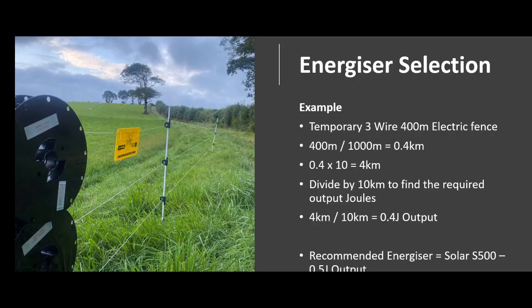Let's start with this example: we're going to erect a single 3-wire electric fence that's 400 meters in length. Applying the theory discussed, 400 meters divided by 1,000 is 0.4 kilometers. We apply the multiplication factor of 10 because it's a temporary fence using polywire, so 0.4 kilometers times 10 is 4 kilometers. We then divide by 10 kilometers to find the required output in joules: 4 divided by 10 is 0.4 joules. So 0.4 joules of output power would be required. Looking through the catalogue, if we wish to use a solar energizer, the recommended one would be the SpeedRite Solar S500 with 0.5 joules of output.